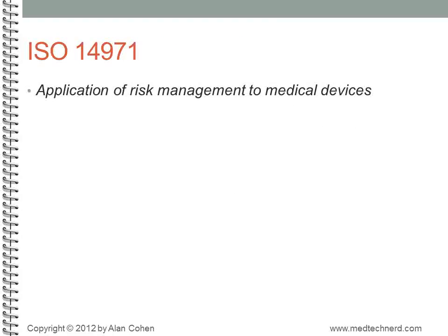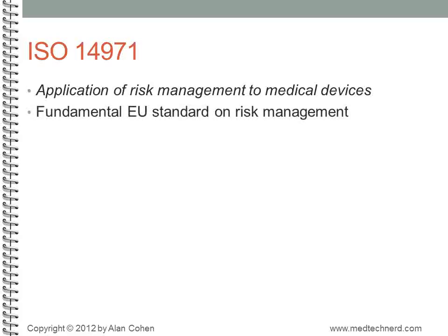This brings us to the first in our core group of medical device standards, ISO 14971, titled Application of Risk Management to Medical Devices. This is a fundamental standard that addresses how risk should be systematically managed throughout the product lifecycle. Following ISO 14971 is required for a medical device CE mark in the EU.